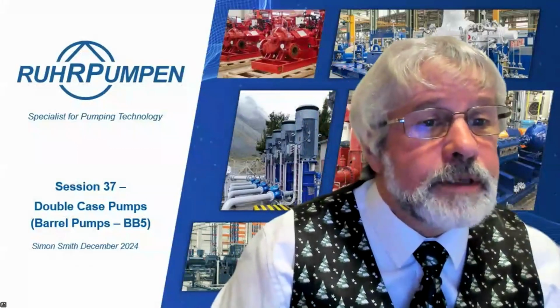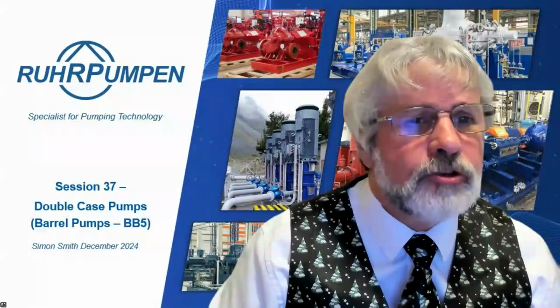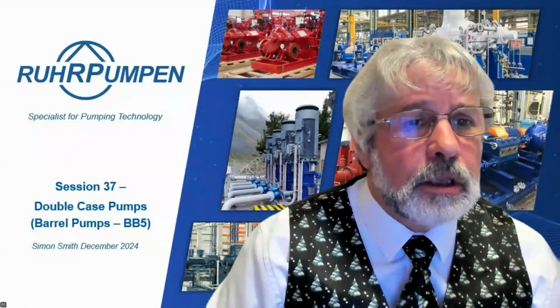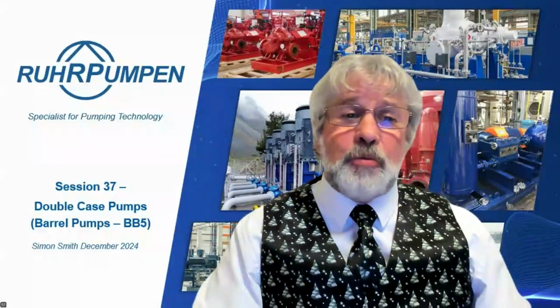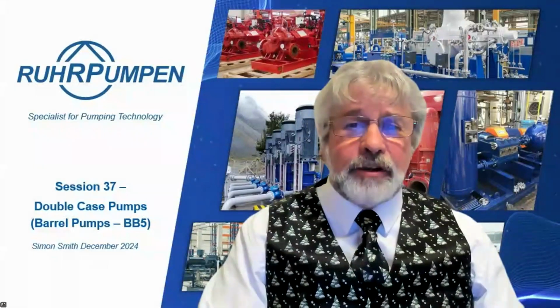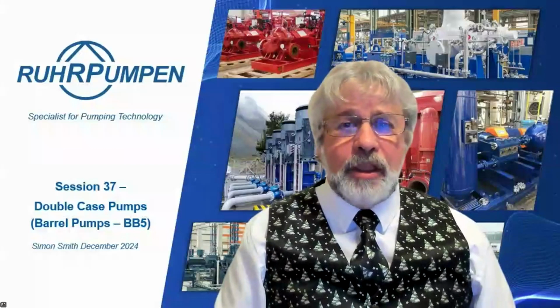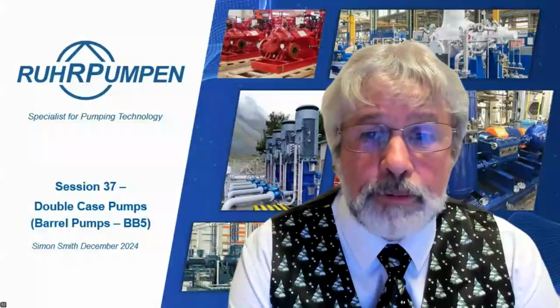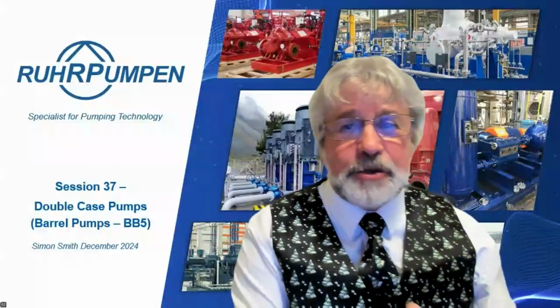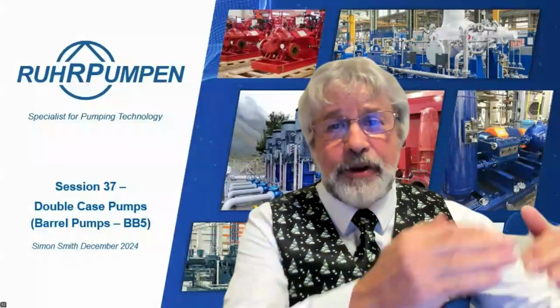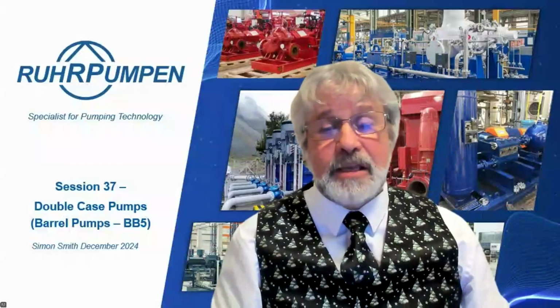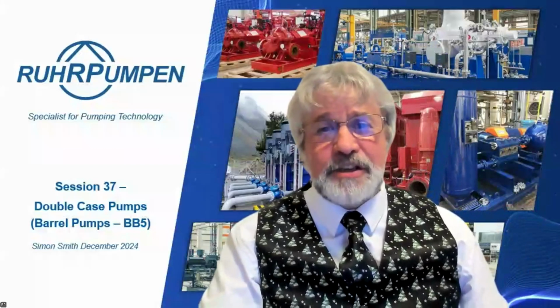Nalathambi Dharmalingam says, please clarify the selection criteria for opposed impeller and balance drum in terms of head or flow. This would be the job of the applications engineer to look at. If it's a low flow, if it's a fairly small pump, we could consider going with the inline impellers, if the residual thrust is going to keep it inside the requirements of an angular contact ball bearing. Once you start getting to needing a tilting pad bearing, the price starts going up and it becomes much more worthwhile to go with opposed impellers. So it's just a value judgment. We'd make that decision on a case-by-case basis, depending on the process conditions.